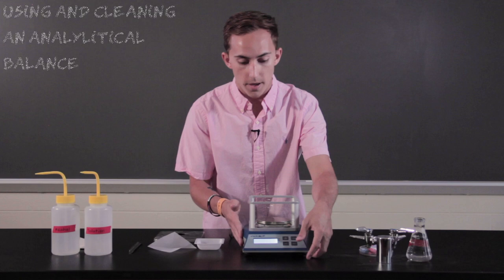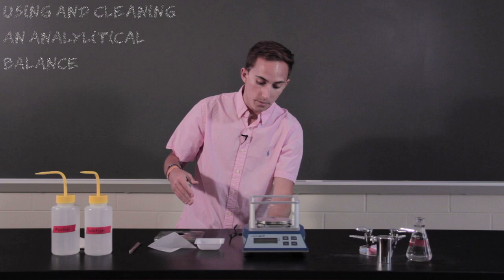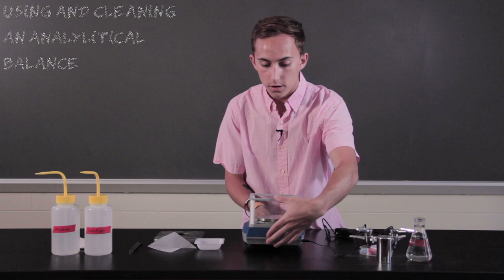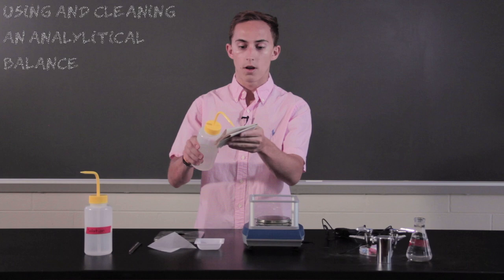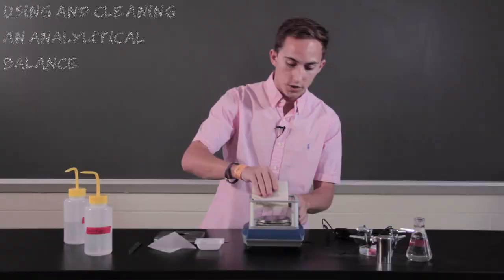So make sure that it is off, and that it is unplugged, so we'll unplug it. Now some analytical balances have a top that comes off. This one does not.